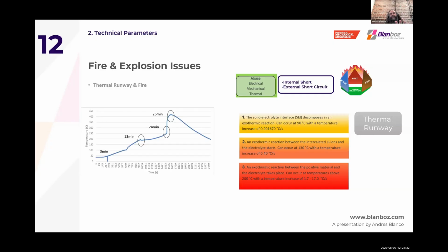I want to give you an indication of timing, because once something is picked up as the fire starting, you don't have much time. In this particular event, something was picked up at the 3rd minute, and from the 3rd to the 13th minute is very vital, because that's when the battery cells enter thermal runaway and start off-gassing, or venting.